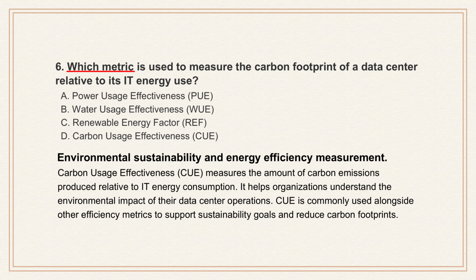But PUE doesn't tell you anything about the source of that energy. This is where we have to look past just efficiency and towards actual impact. The correct metric here is carbon usage effectiveness, or CUE. It's so important because it directly links the data center's energy use to the greenhouse gases it's responsible for, calculated by taking the total CO2 emissions and dividing that by the IT equipment's energy consumption.